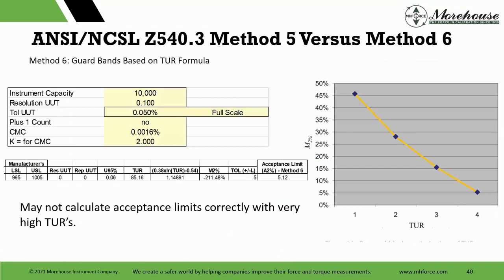Method 5 versus method 6. Something to be aware of with method 6 is that it may not calculate acceptance limits correctly with very high TURs. So if you're using method 6, you kind of have to modify the formula. This is an example showing a super high TUR, 85.16, and it's basically saying your acceptance limit is above the specification limit. That all goes away with simple math. You write an if statement: if my TUR is 85.16, use a TUR of 4.5, and then it'll work correctly. So we built that into the sheet.